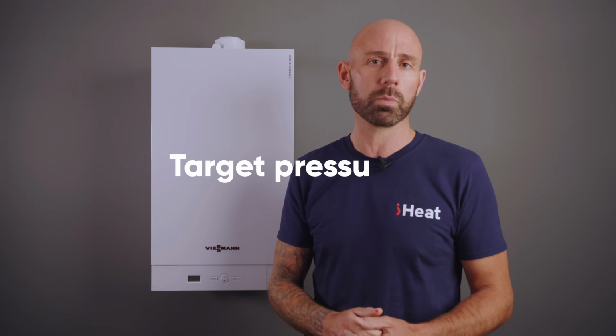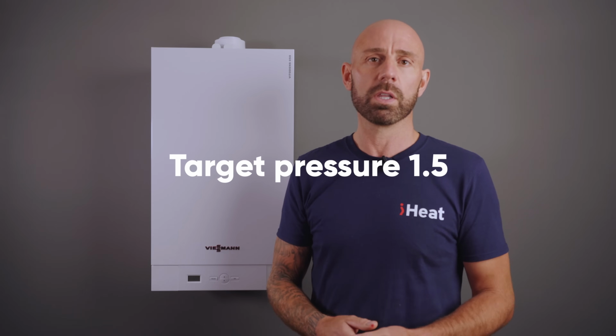The target pressure should be around 1.5 bar and the system should be cold or the boiler should be switched off. After this, you can bleed the radiators to ensure that there is no remaining air left in the system. Then check to make sure the pressure is around 1.5 bar before turning the boiler back on. If the pressure has dropped after bleeding the radiators, then repeat this process until getting the target of 1.5 bar.